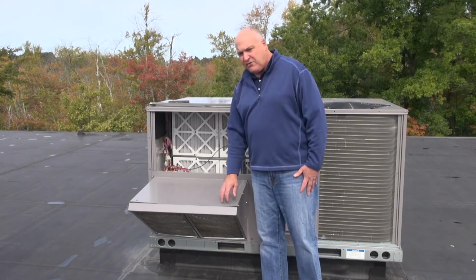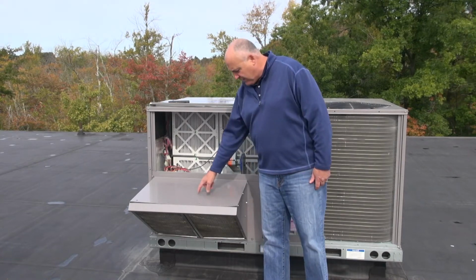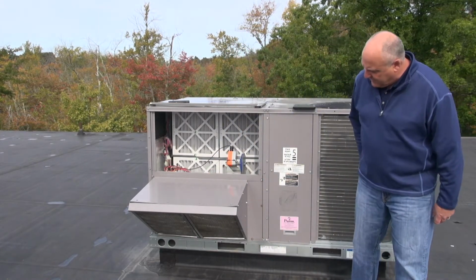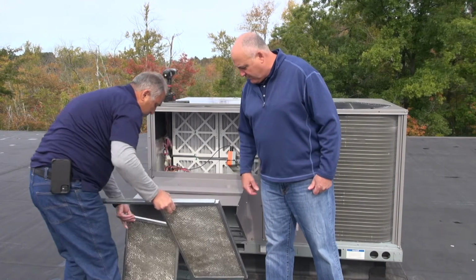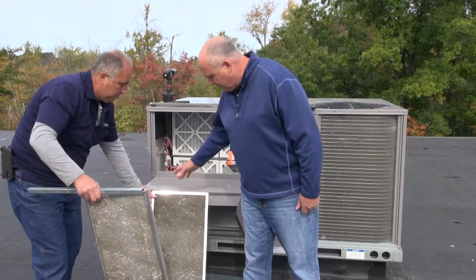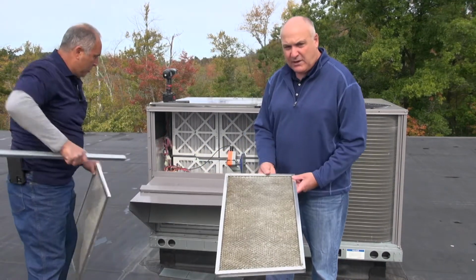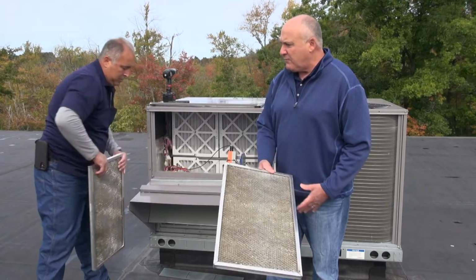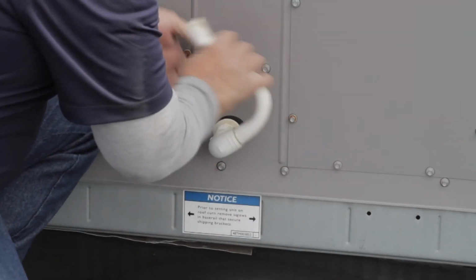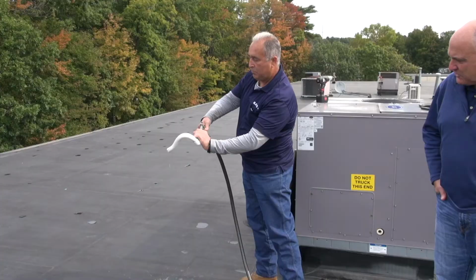The economizer brings fresh air into the building when the outside air is sufficient for cooling. The economizer also contains additional filters which need to be cleaned or replaced. The condensation drain trap is inspected and flushed.